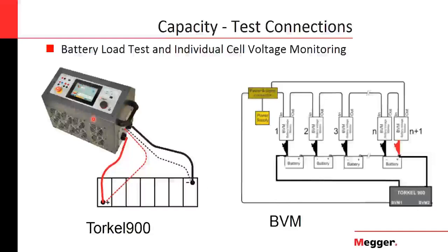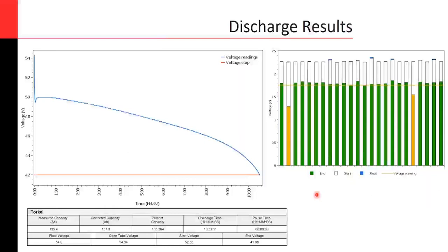If there are means, as I said, to measure the voltage on each cell automatically and constantly during the test, this is one of the arrangements. Of course, you need to have something connected to each cell, and all of that information will go to the same instrument, so you can have all the information there, and at the end have a result like this. This graph to the left is the discharge curve, how the voltage behaves during all the discharge. And this red line is the limit where the discharge should stop.